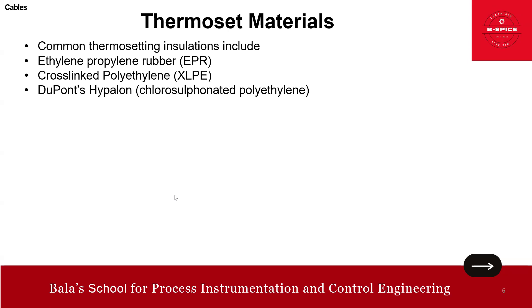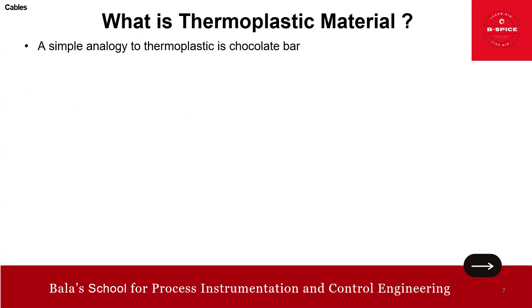Common thermosetting insulations include: ethylene propylene rubber (EPR), cross-linked polyethylene (XLPE), DuPont's chlorosulfonated polyethylene (Hypalon), nitrile or butadiene nitrile rubber (NBR), styrene butadiene rubber (SBR), and silicone rubber. Just to remember two key points: XLPE is thermoset; PVC is thermoplastic. That distinction is good enough.